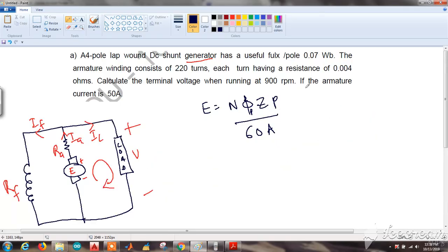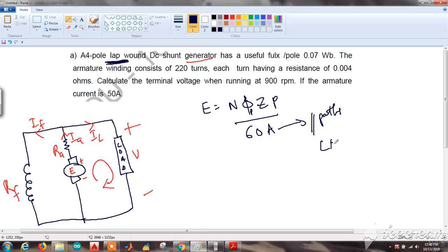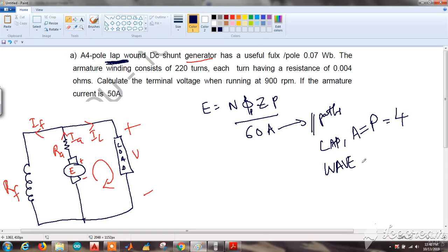The EMF generated is given by E = NΦZ P / 60A, as seen in previous questions. Here, A is the number of parallel paths. For lap winding, the number of parallel paths equals the number of poles — in this case 4 poles, so A = 4. For wave winding, the number of parallel paths is always 2. Please remember this.